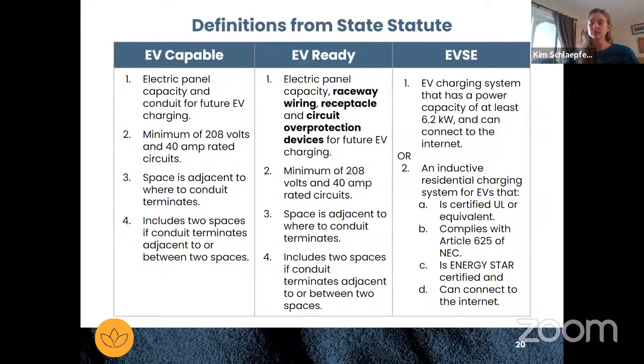Within the residential EV code language, we'll be running with the exact same definitions for EV capable, EV ready, EV installed. So as a reminder, our definition for EV capable is that the space has to have electric panel capacity and conduit for future EV charging, and the panel capacity has to be a minimum of 208 volts with a 40 amp rated circuit. Where this differs from EV ready—and I know we've covered this, but to reemphasize—EV ready spaces also include raceway wiring, receptacle, and circuit overprotection devices for the future EV charging. Otherwise, the rest of those requirements stay the same.